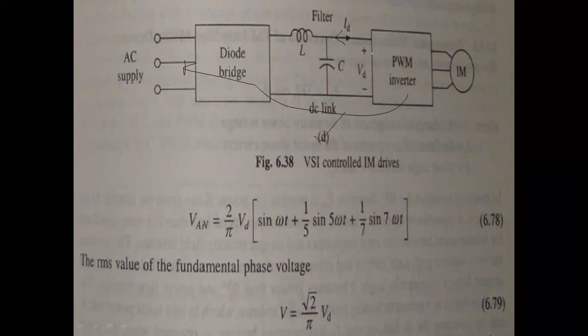Thus, for a regenerative braking capability, a converter capable of dealing with DC voltage of one polarity and DC current of either direction is required. What we require is that the current should be reversed, but the voltage should be maintained in the same direction only. So for this we have to take the dual converter, which has this capability, and we have been employing this in the past also.